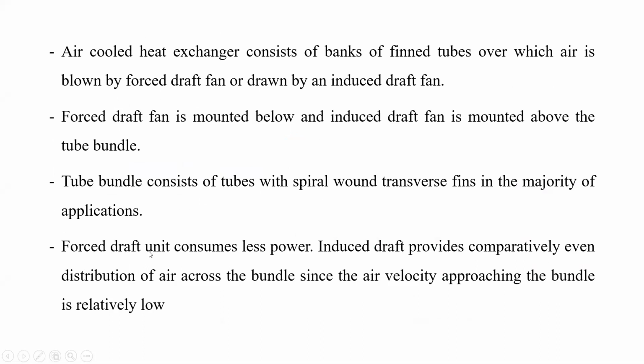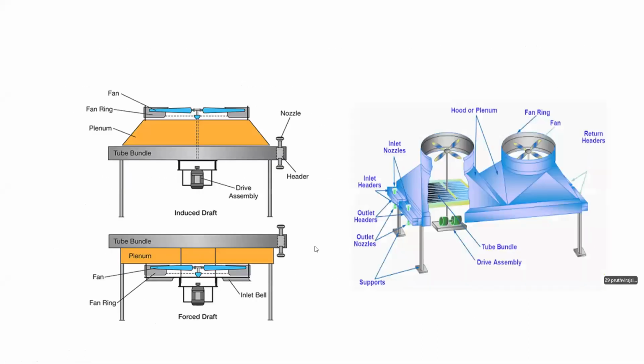Generally, the forced draft unit consumes less power, while the induced draft provides a comparatively even distribution of air across the bundles, since the air velocity approaching the bundles is relatively low. In induced draft, the fan is located at the top, so it has to suck the fluid and the air from the top.